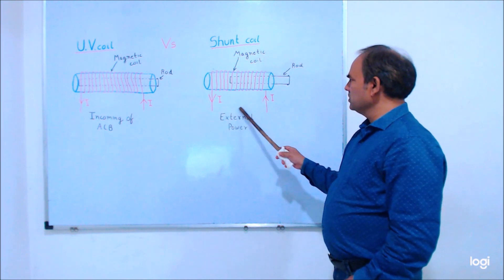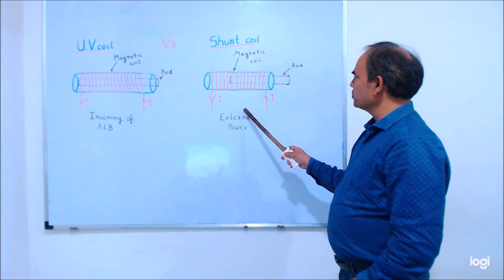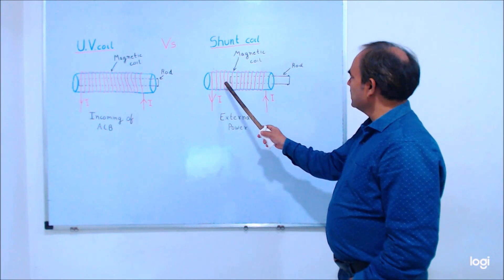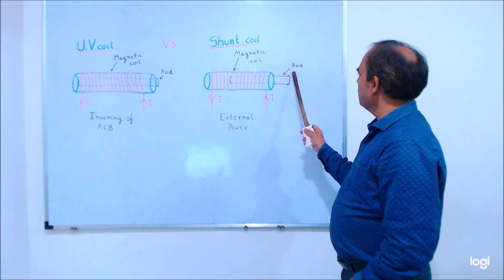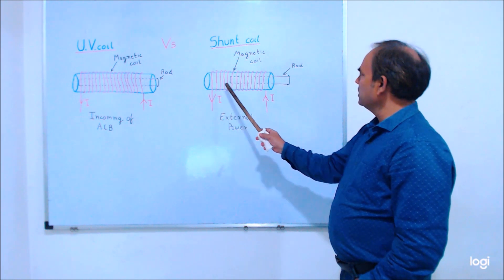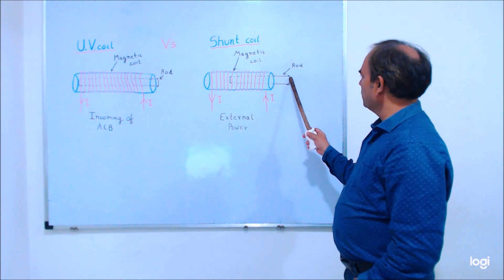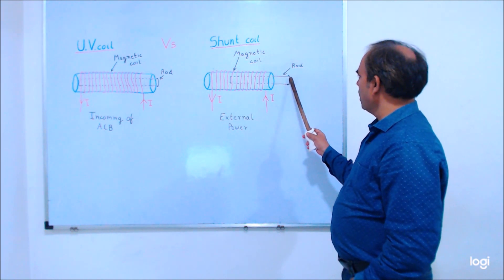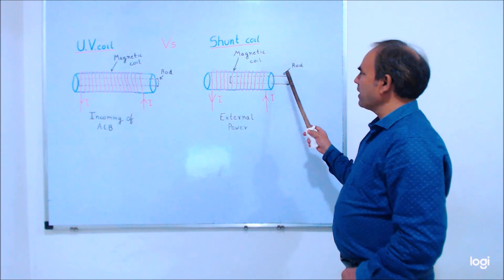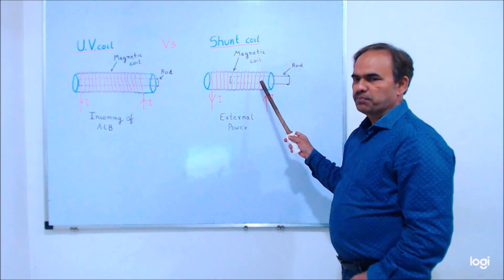When we give power to the shunt coil through an external source, it will energize and pull the rod inwards, which then pulls the tripping mechanism of the circuit breaker, causing it to trip.